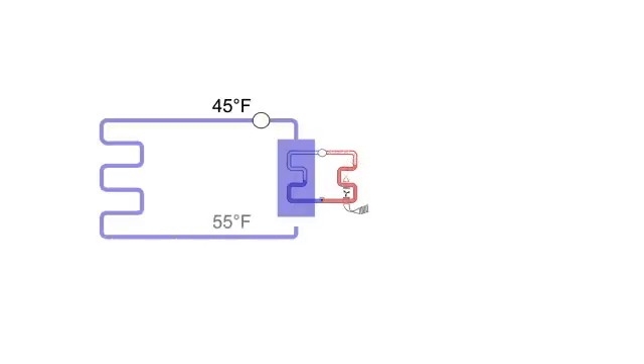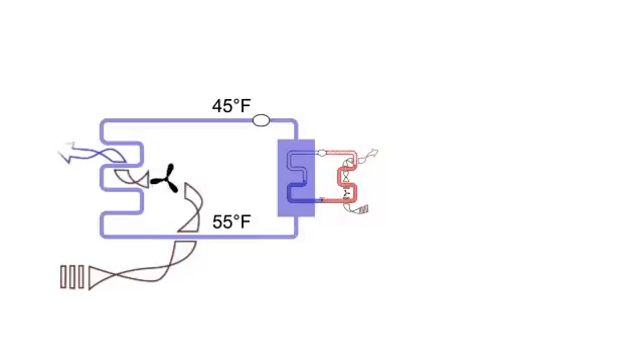Air performs reasonably at carrying cold air, but water is better at heat exchange and does a superior job keeping cold over long distances. For this reason, many buildings, and some campuses or city districts, utilize chilled water. In this regime, pumps carry water chilled on the evaporator side, which is to say the cold side, of the compression refrigeration loop, to sometimes distant air handling units. The air handling unit then blows air across coils of chilled water, rather than coils of chilled coolant as we saw in previous examples, thereby cooling 70-degree return air to 50 degrees for distribution through ducts.